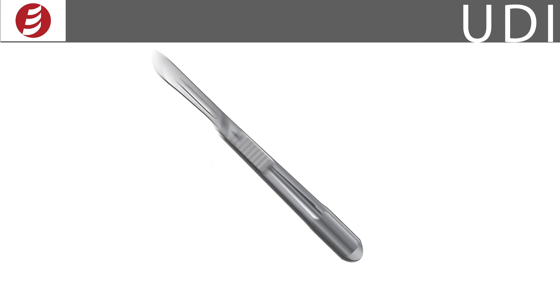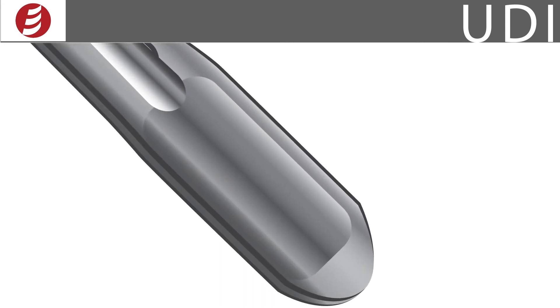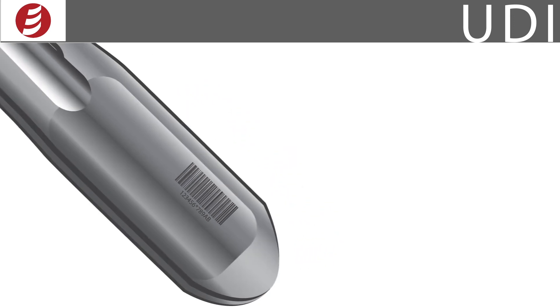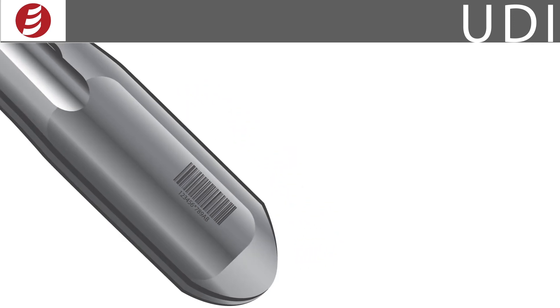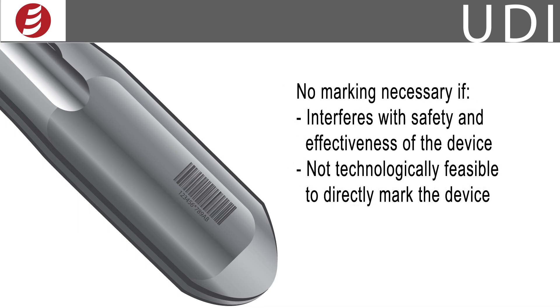Devices intended to be used more than once and intended to be reprocessed before each use are required to bear a permanent UDI in either plain text or machine-readable formats. There are some exceptions. For example, if the marking interferes with the safety or effectiveness of the device, or if there is just no feasible way to mark the device, then the marking is not required.